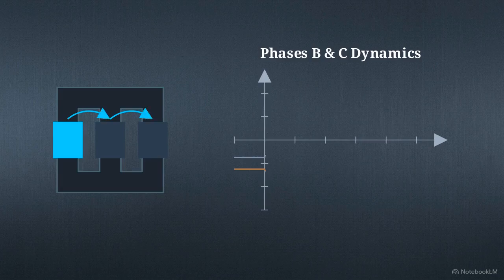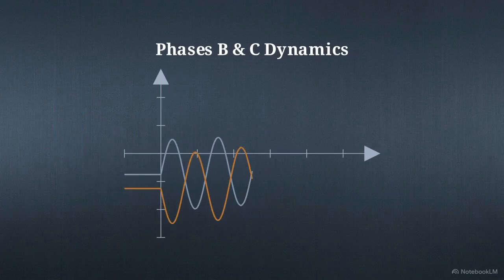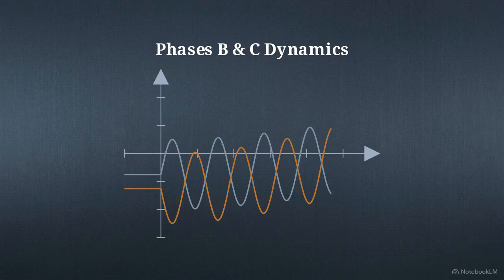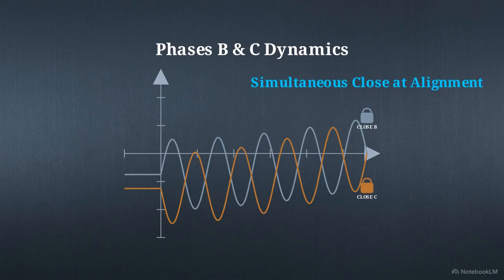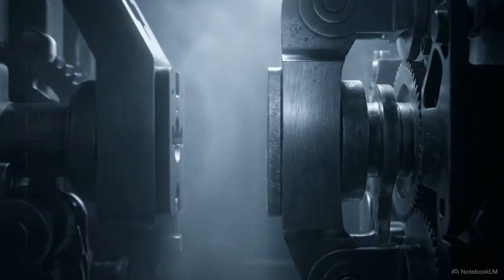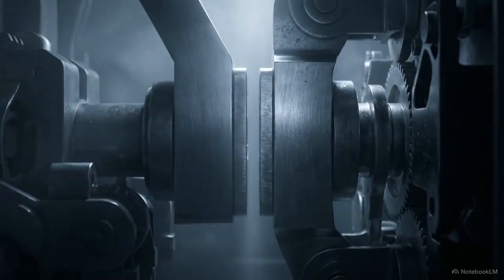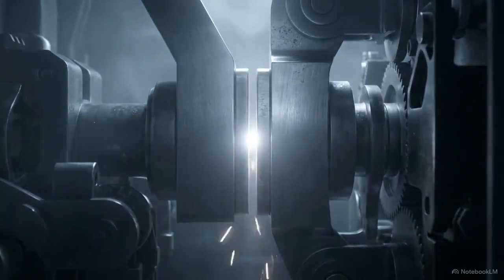But there's a complication. Because the 3 phases share a single iron core, turning on phase A causes the magnetic flux in the 2 unclosed phases to dynamically shift and oscillate. The controller waits exactly 4.5 electrical cycles for the dynamic flux in those remaining 2 phases to align, and then fires both breakers simultaneously.